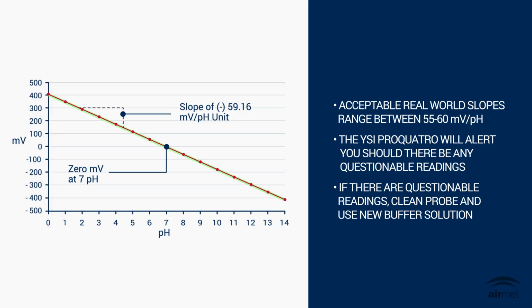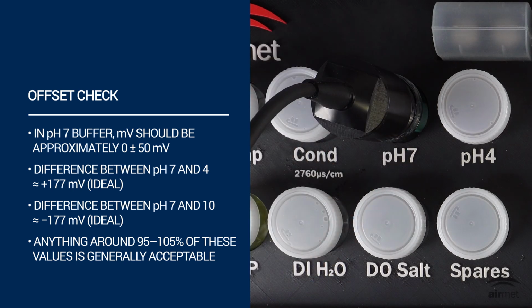A slope below that, around 53 millivolts per pH unit, which is 90%, is typically flagged as a questionable reading and suggests an aging electrode, fouling, or poor buffer quality. In pH 7 buffer solution, millivolts should be around 0 plus or minus 50 millivolts. The difference between pH 7 and pH 4 is around 177 millivolts, which is ideal. The difference between pH 7 and 10 is also around negative 177 millivolts. Anything around 95 to 105% of these slope values indicates a generally acceptable measurement.